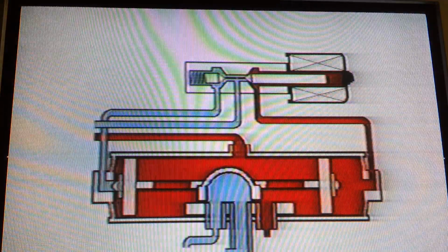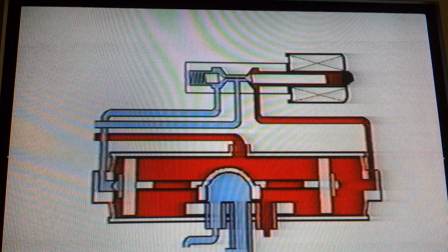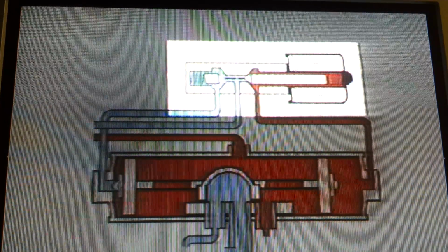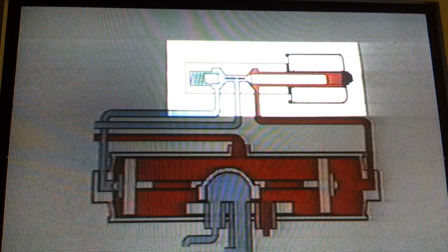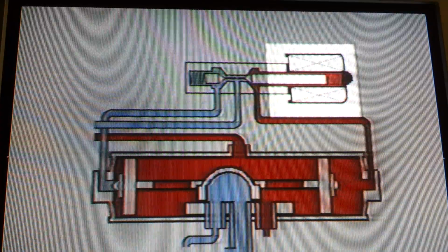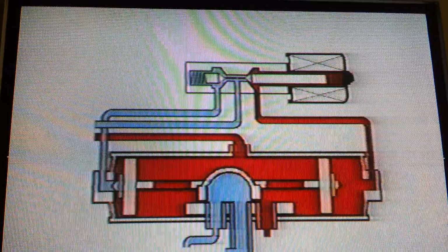Slide comes from the pressure difference of the high and low side of the heat pump itself. The control of system pressures to move the slide is done by a pilot valve mounted to the valve body. The pilot valve is electrically operated by a 24-volt coil connected to the heat pump control circuit. Both coils in a heat pump have the capability of being either a condenser or an evaporator.